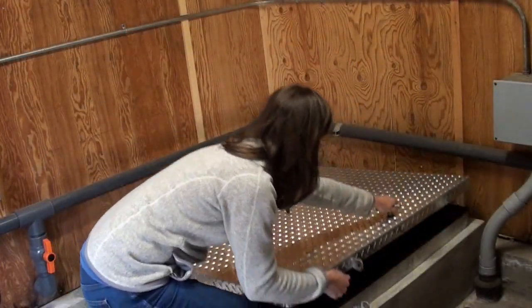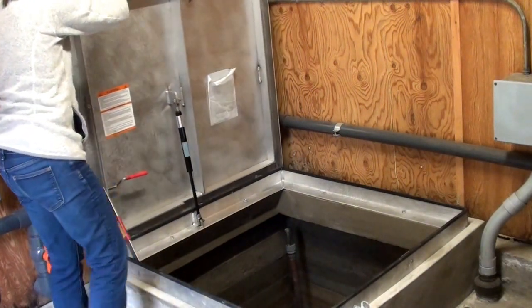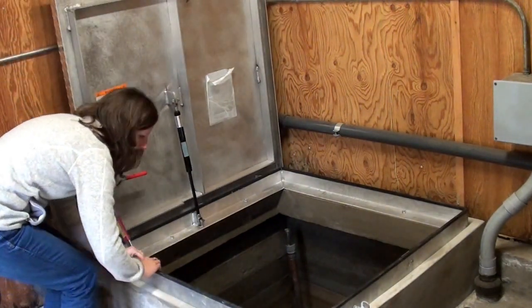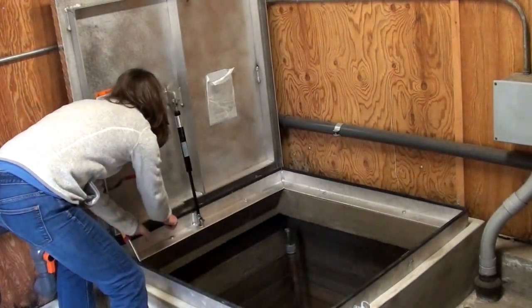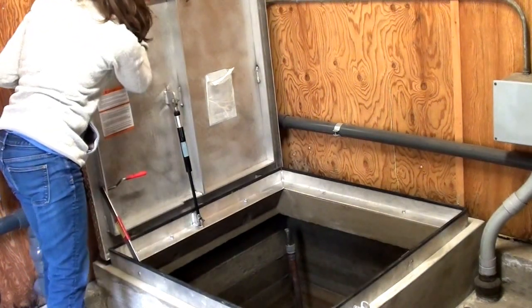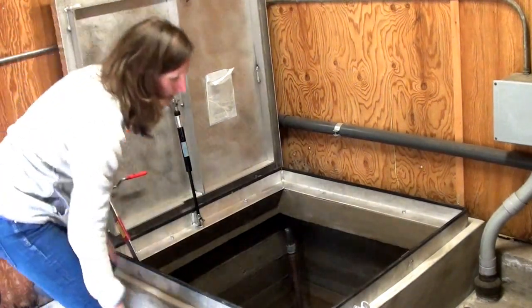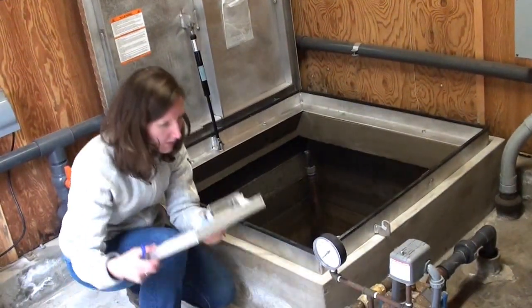Start by performing a visual inspection of the storage tank, looking for leaks, any damage, signs of vandalism, or forced entry into the tank. Increased water age in storage tanks can impact the quality of the system, so that is something to consider also. As the water ages, disinfectant residuals decrease and the potential for contamination increases.